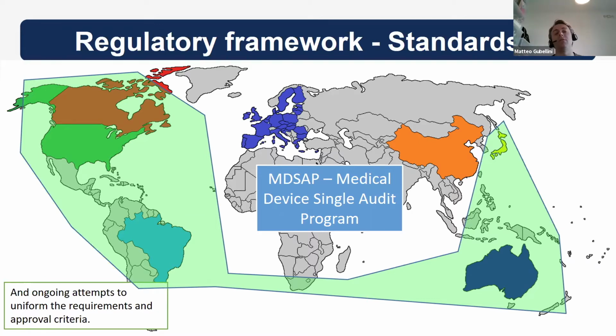it is basically based on 13485, but on top of that, there is a compendium. I can't remember exactly the name, but it is a companion that you can find on the FDA website. It is, I don't know, 100 pages that show you the additional requirements that each country has on top of 13485, and basically that's what you will be audited on: 13485 plus the delta. And it is important to note that you don't have to go with all the countries. You can decide to get an MDSAP certificate for US and Canada, and that's it, and that will be what you will be audited on.